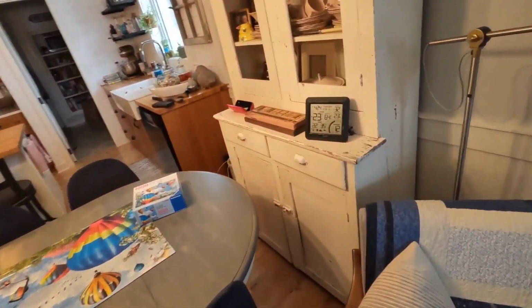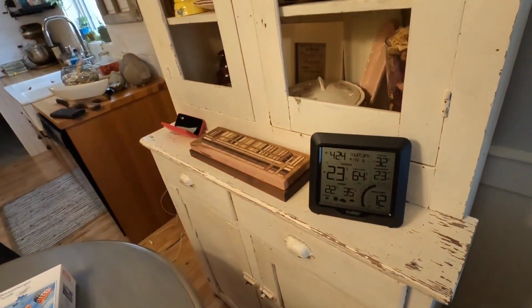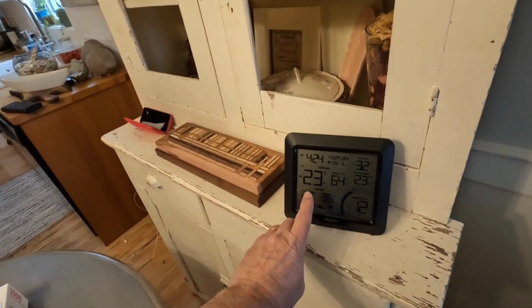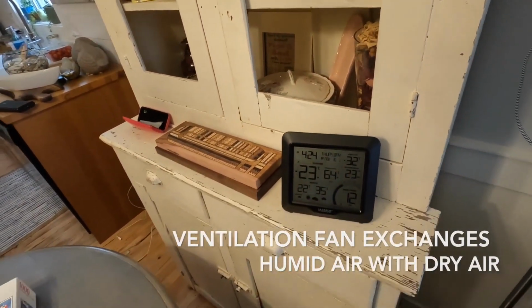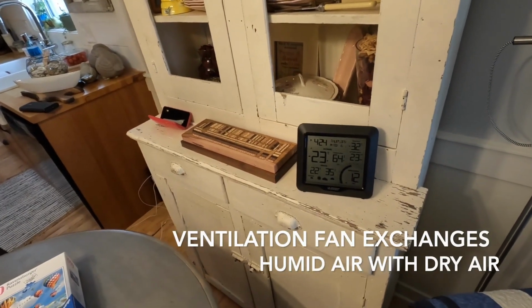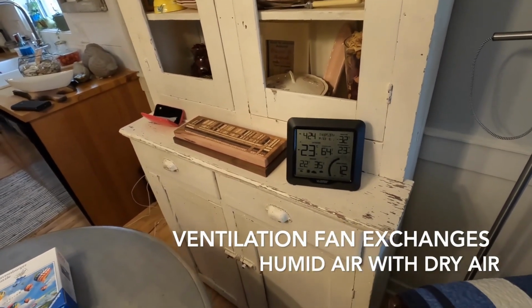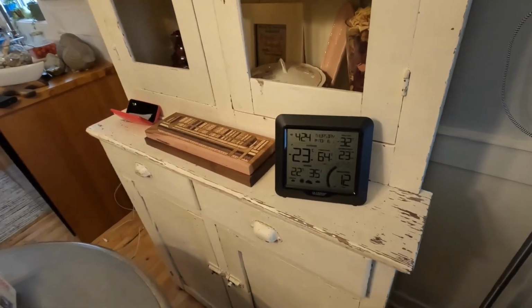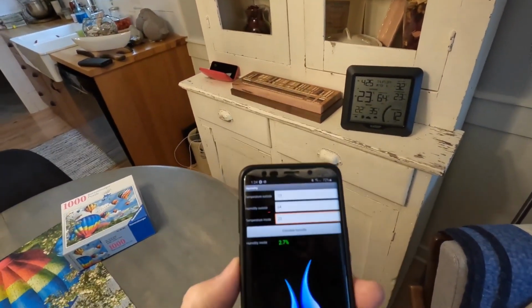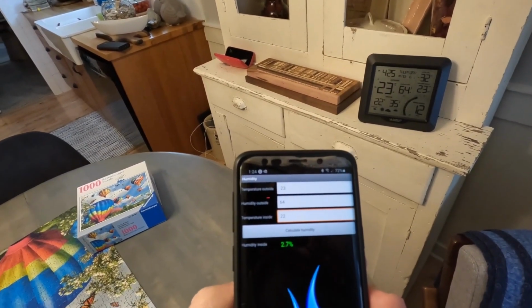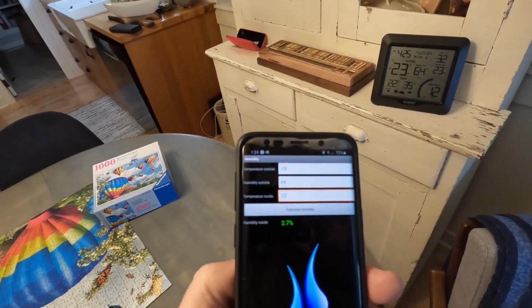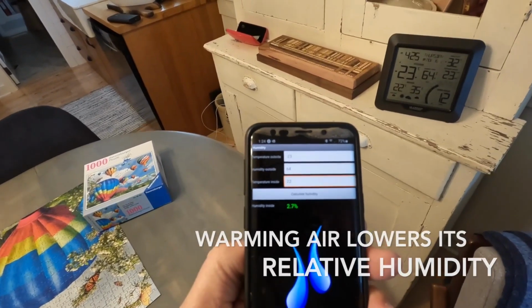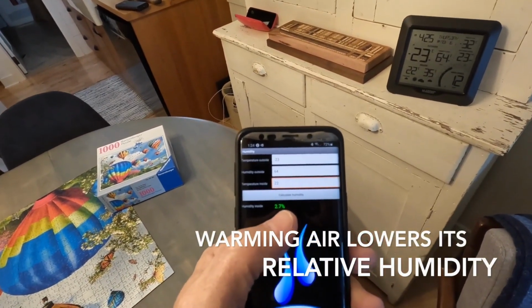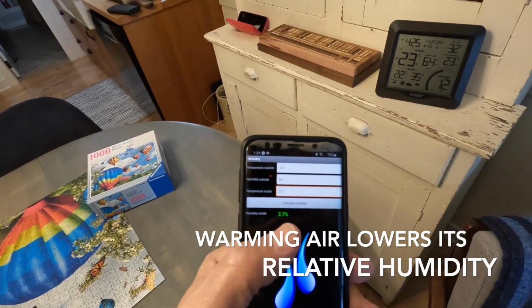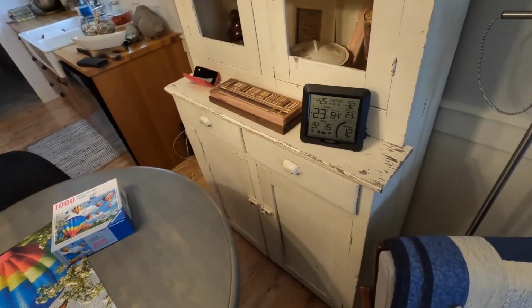Now, if we go back to here, one of the ways that we reduce the relative humidity, and you can see it here, it's at minus 23 outside, 64% relative humidity. What that means is that air is bone dry outside. So how do I know? Well, if I take my app here, and I punch in outside temperature minus 23, humidity outside 64, and I warm it up to room temperature, see right there, it's 2.7% relative humidity. So that's bone dry air. Once it warms up, it has lots of capacity to absorb moisture.